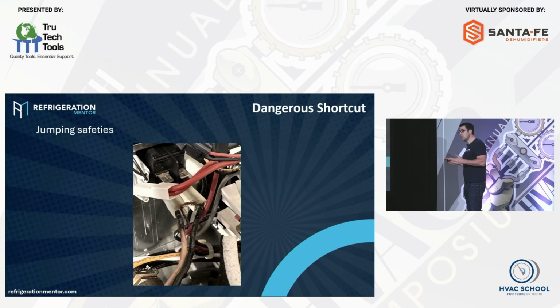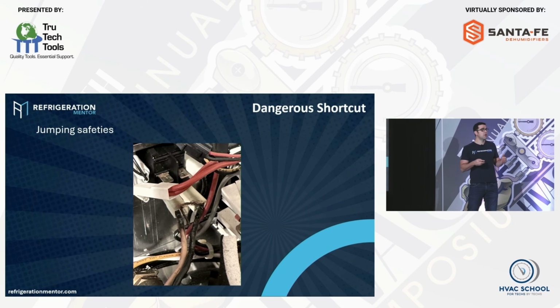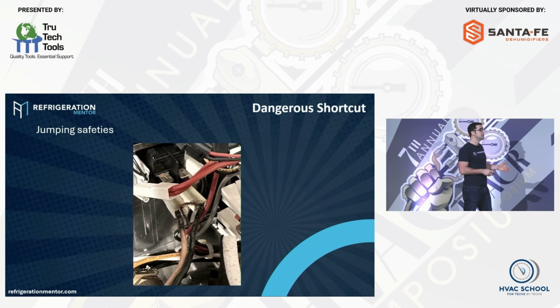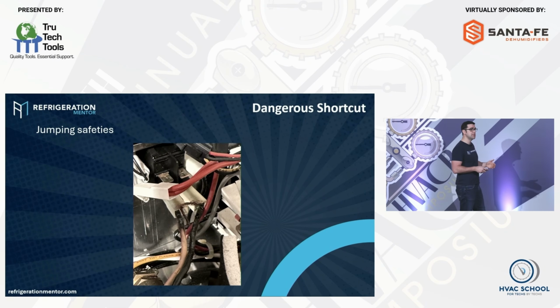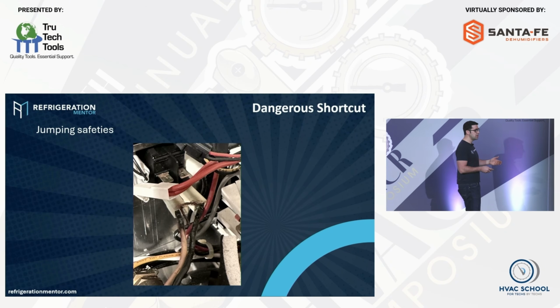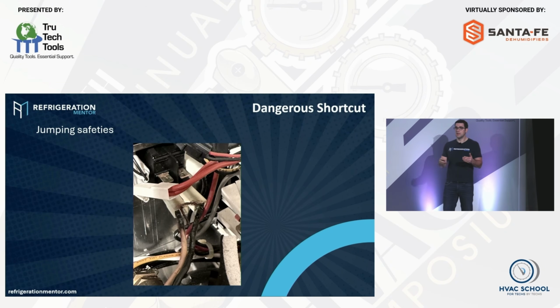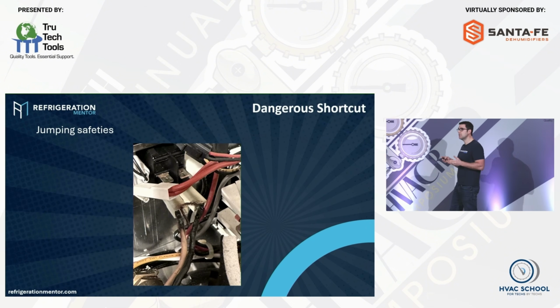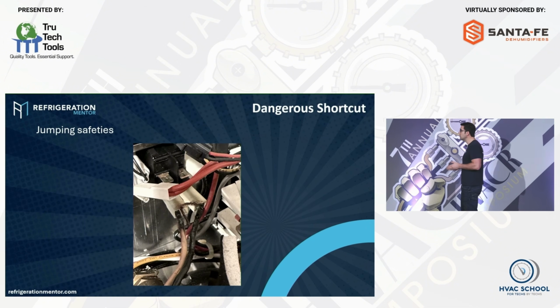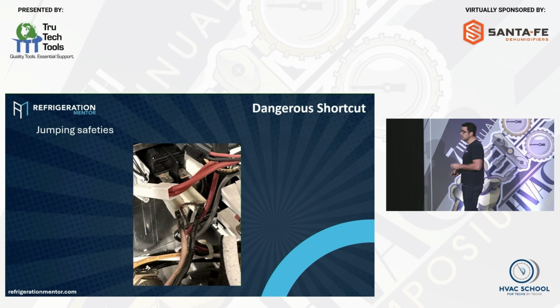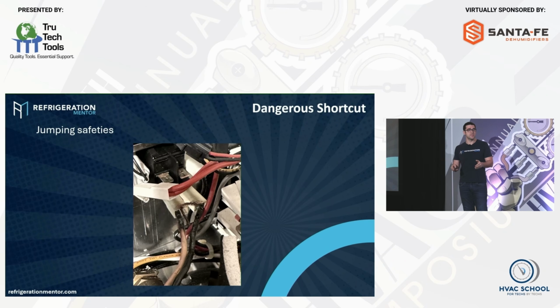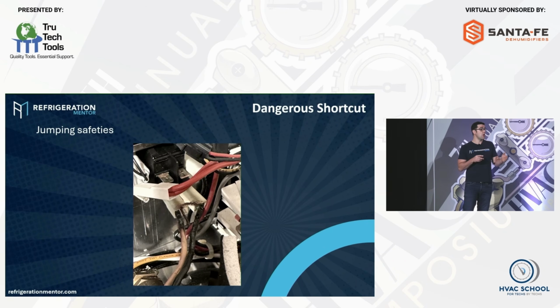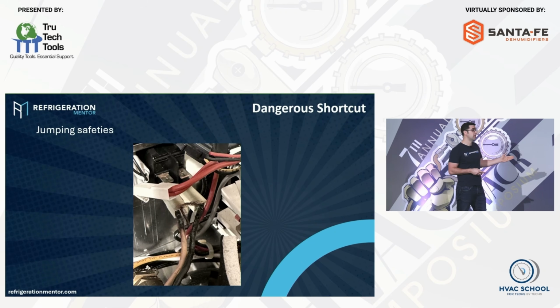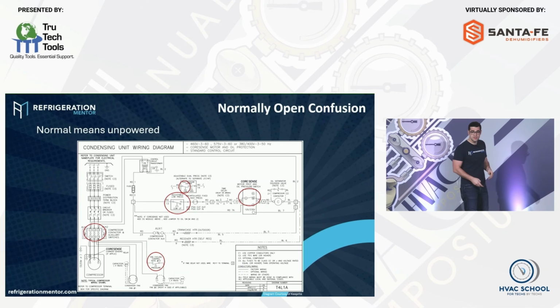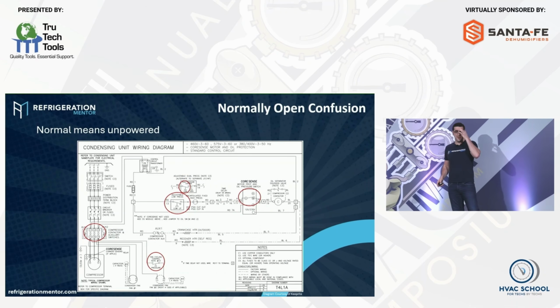Don't ever jump out safeties. Safeties are there for a reason, okay? If you need to do a certain test, like jump a low pressure control to test discharge valves to see if they're working, yes, you would do something like that. And these are just for tests. You pull it off afterward. You never leave safeties jumped because you could hurt yourself, you could hurt the equipment, or even worse, hurt somebody, yourself or another technician.